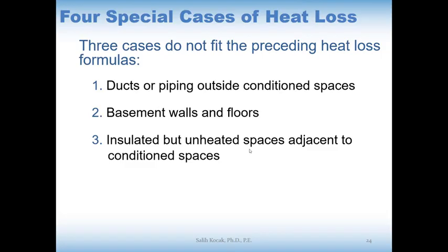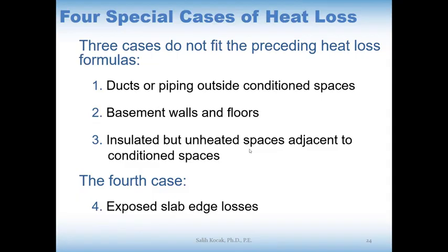And there's another case, that fourth case is exposed slab edge losses. In a slab-on-grade type of foundation, the foundation is larger than the house itself, so the exposed edges of that slab cause heat losses, and that is the fourth case. The fourth case is handled a little differently than the other three cases, because we can just make assumptions for how we are doing it.